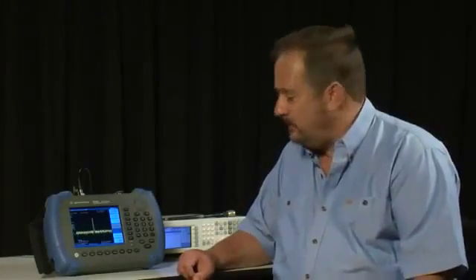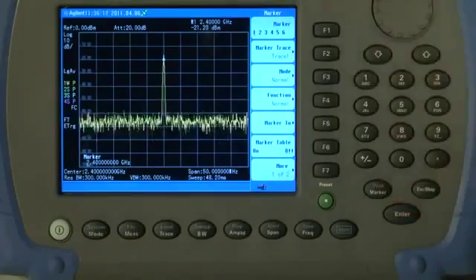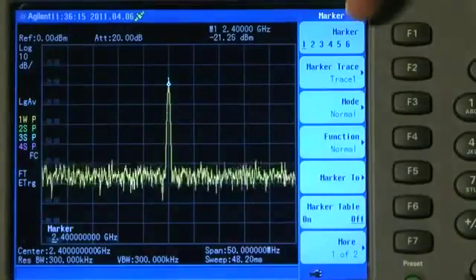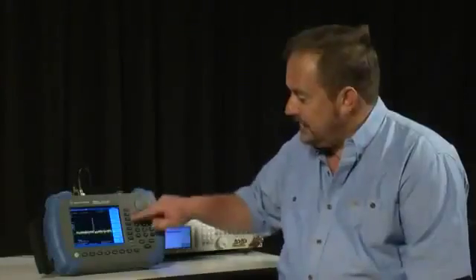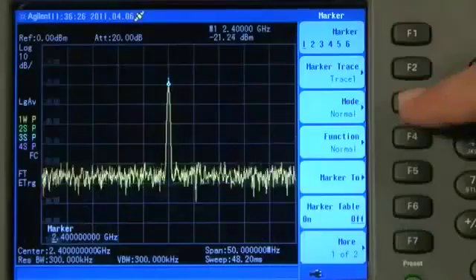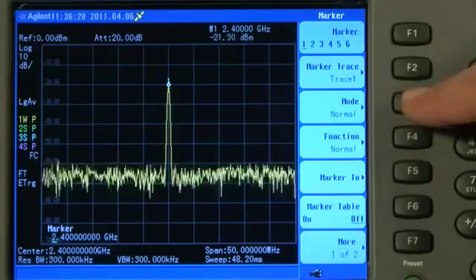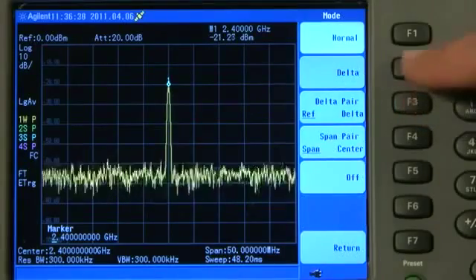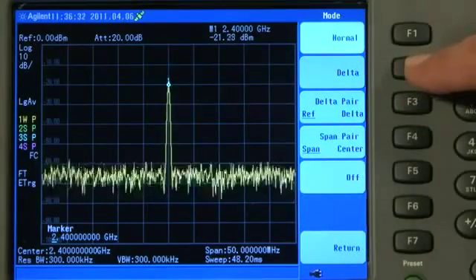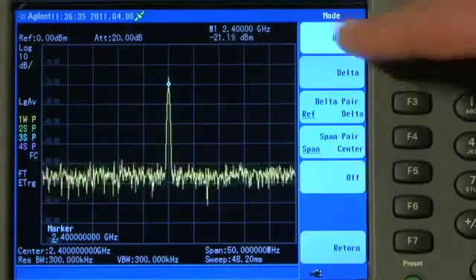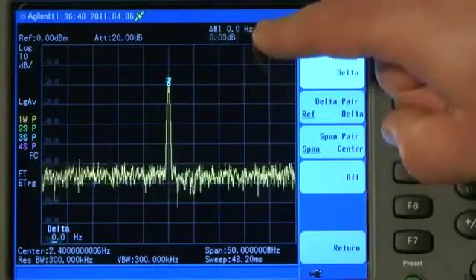There are a couple of other useful marker features we ought to take a look at while we're doing this. If I press the Marker button again, you will see first of all we have up to 6 markers that we can have turned on at the same time. Currently the Marker Mode is set to Normal for Marker 1. If I press the Mode button, you will see we can have a Delta Marker. This can be quite useful. If I press Delta, instead of the marker saying 2.4GHz, it now says that Marker 1, or the Delta Marker 1, is now 0Hz and 0dB.